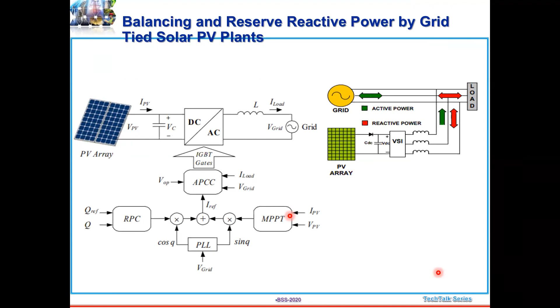This is basically a single line diagram for that particular inverter, the solar ABB inverter, PVS800 series. They have both day and nighttime capacity. Even during nighttime, they can provide reactive support, because they'll be drawing power from the grid to charge the DC system capacitors, and then they'll provide the reactive support to the grid. It's very easy for them, since it's a VSC-based system.